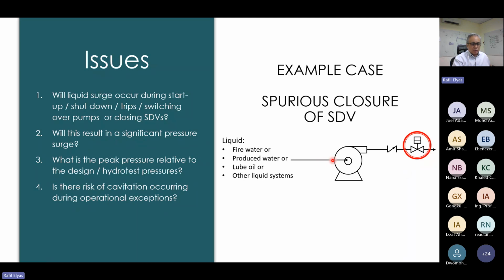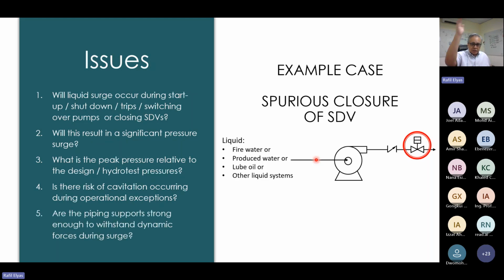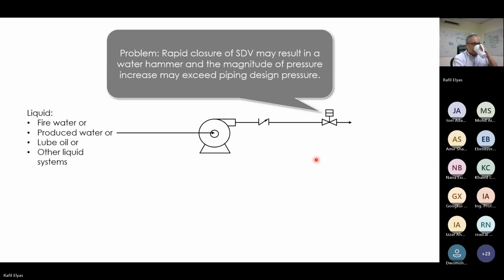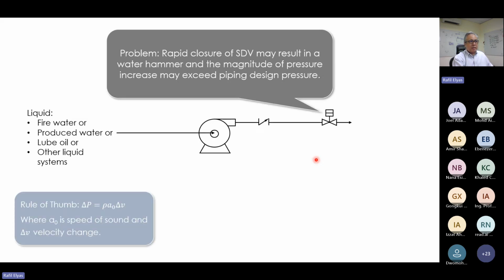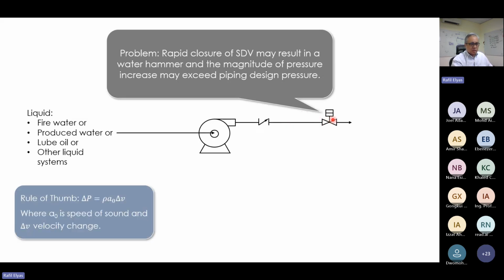When I'm starting up the pump, do I have enough NPSH over here to prevent cavitation from happening? I want to make sure I prevent the pressure from dropping below the vapor pressure of the liquid. When you have cavitation, you start getting pump vibrations and you typically trip. If there's any kind of pressure surge, are the supports going to be strong enough to withstand the dynamic forces? In this case, we've done these cases for fire water, produced water, lube oil, LNG loading. So the issue is you could have a sudden closure or some kind of transient.